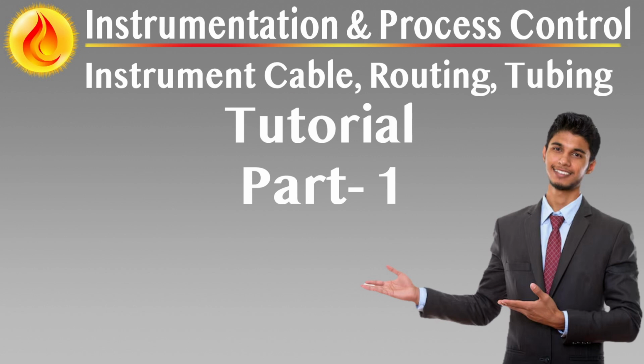Cable construction and application compatibility. Cables used for signal transmission in instrumentation must be constructed to meet electromagnetic compatibility, EMC, mechanical durability, thermal tolerance, and environmental protection requirements. For signal level classes 1, 2, and 3, typically low-voltage analog and digital signals, cables must be screened with a metal shield and include a drain wire to control interference.